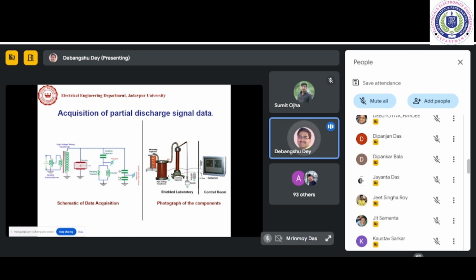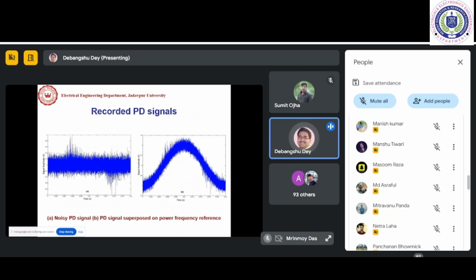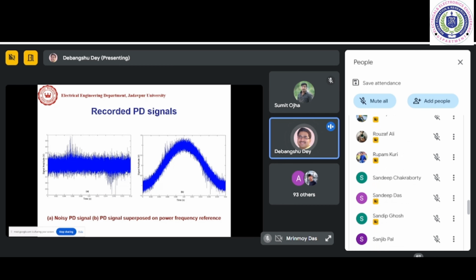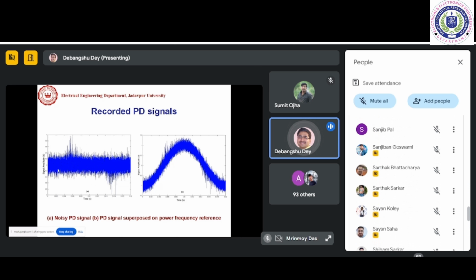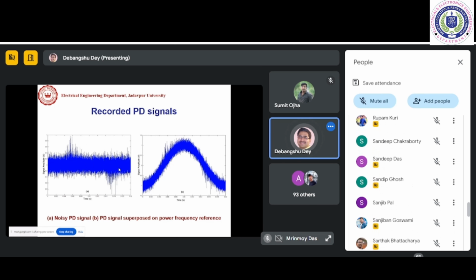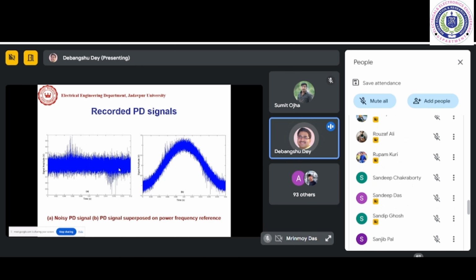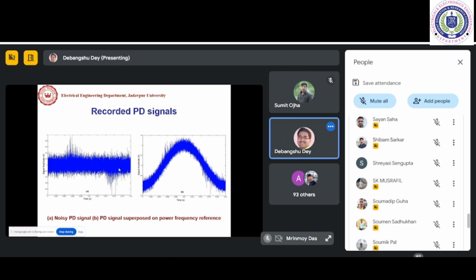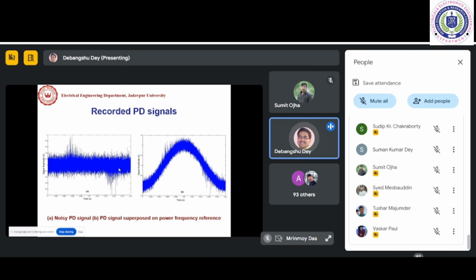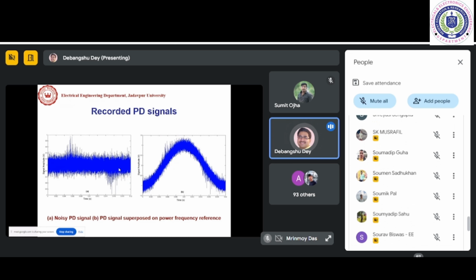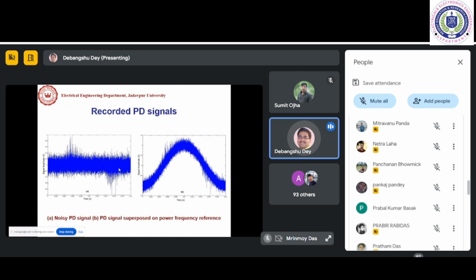So whenever we record the signal, it will look like this. You can see those signals are very noisy, because the partial discharge signals we get are in the order of microvolts, millivolts, since the amount of charge discharged is of the order of nanocoulombs, picocoulombs, like that.